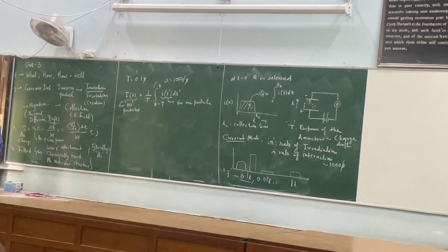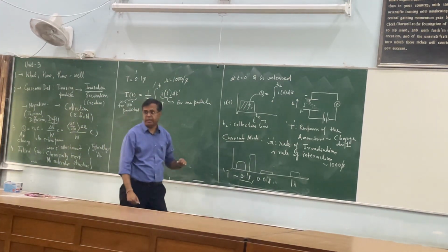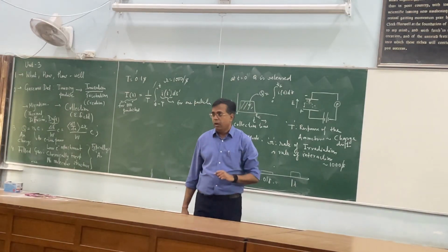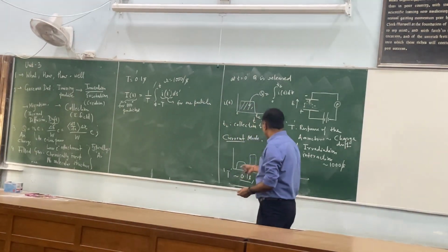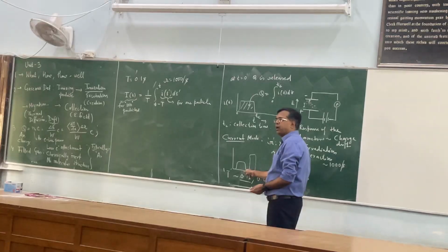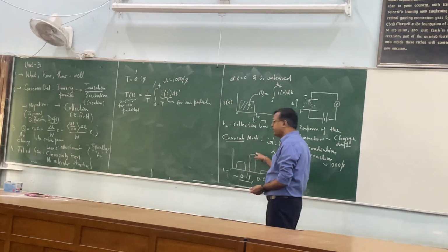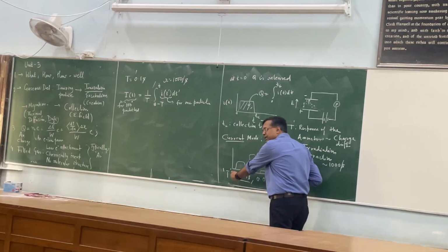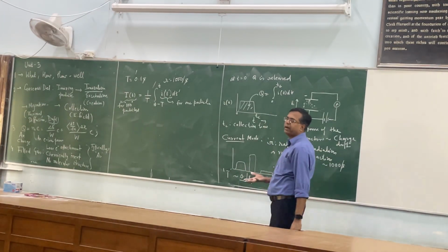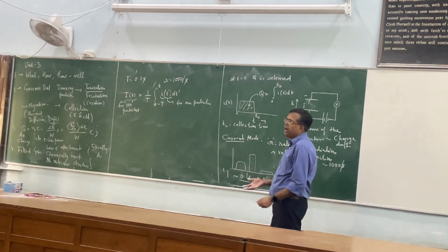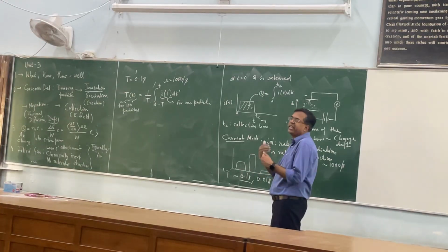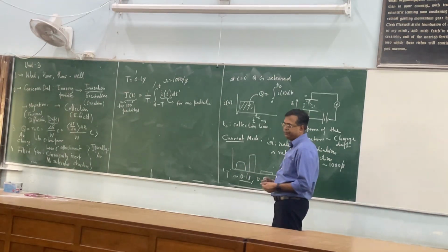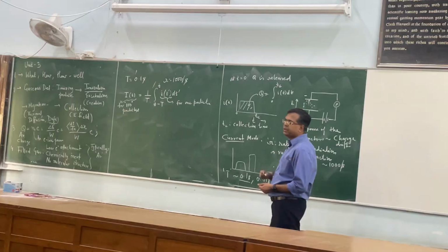Yeah. So our picoammeter in the current mode gives this, which means that I do not care what is the exact nature of this one or of that one. I only care, in 100 such pulses, what the total current actually flowing is, and I just divide by it. That is how a typical current meter works, and that is what happens in the current mode.